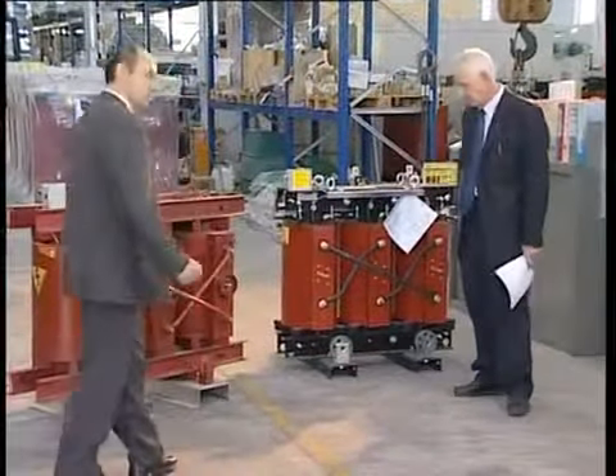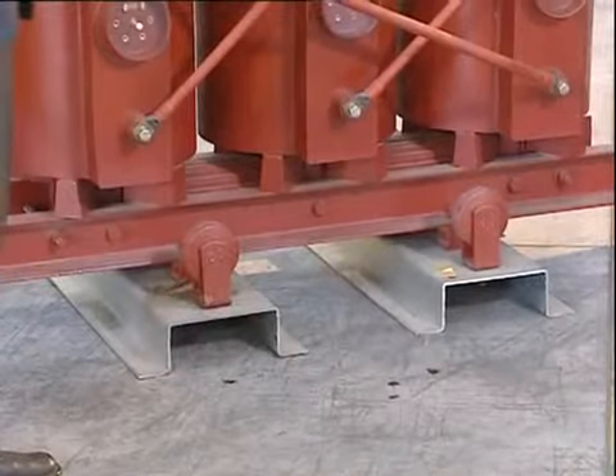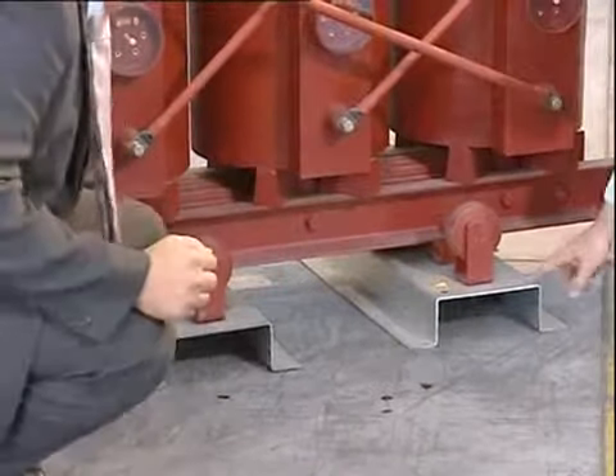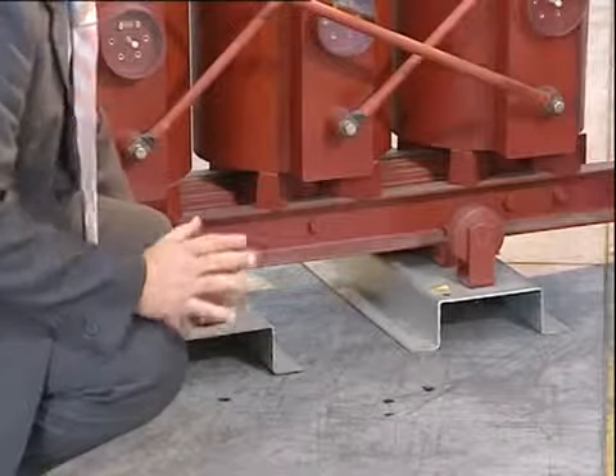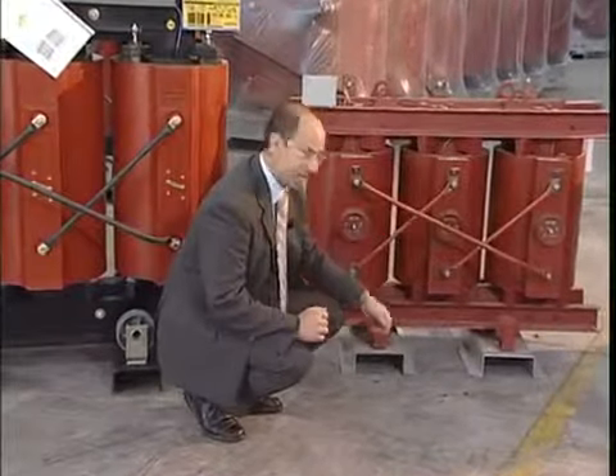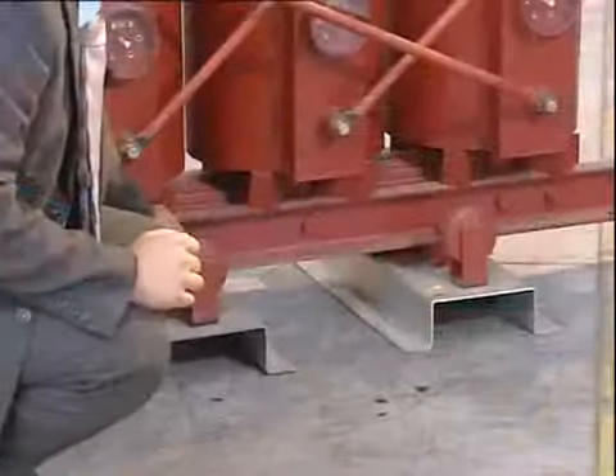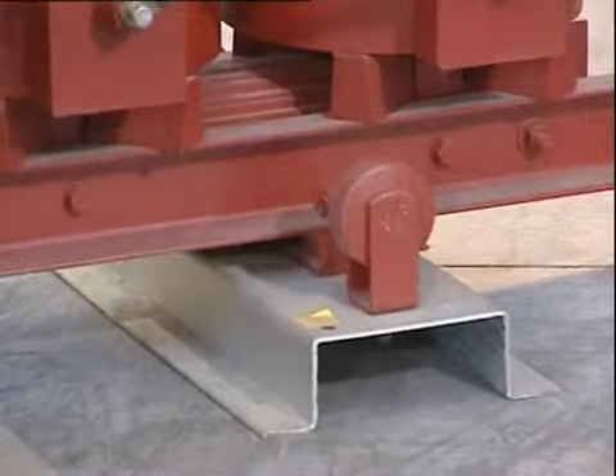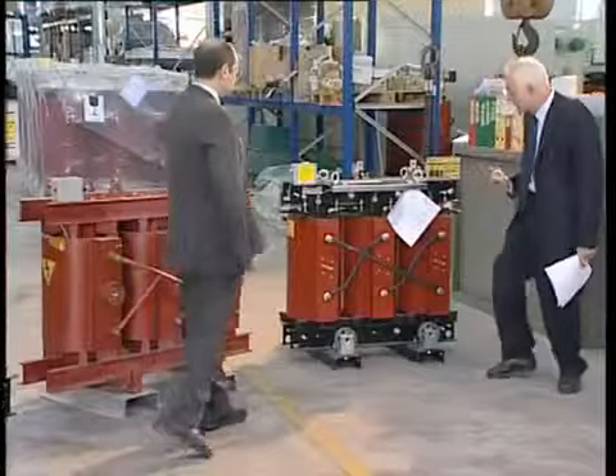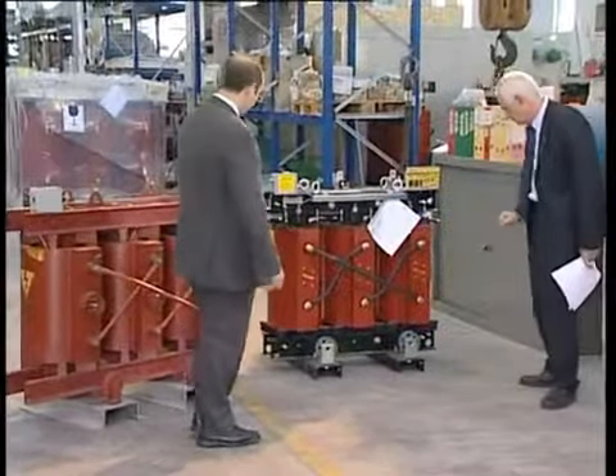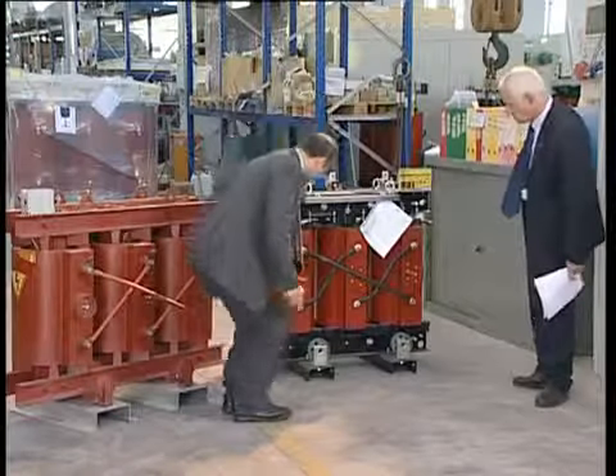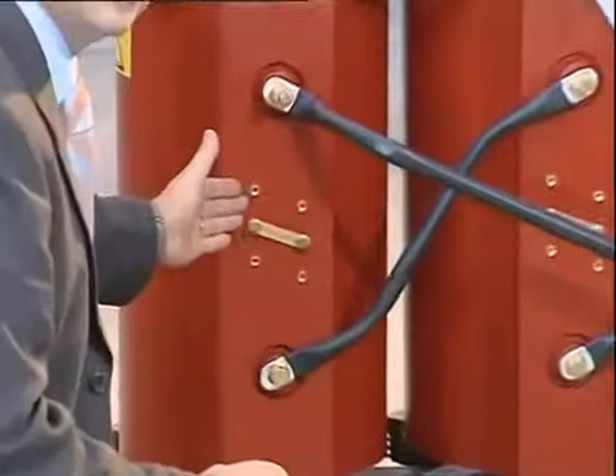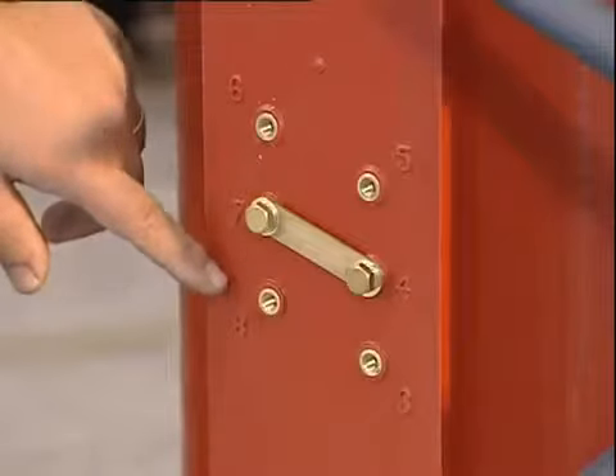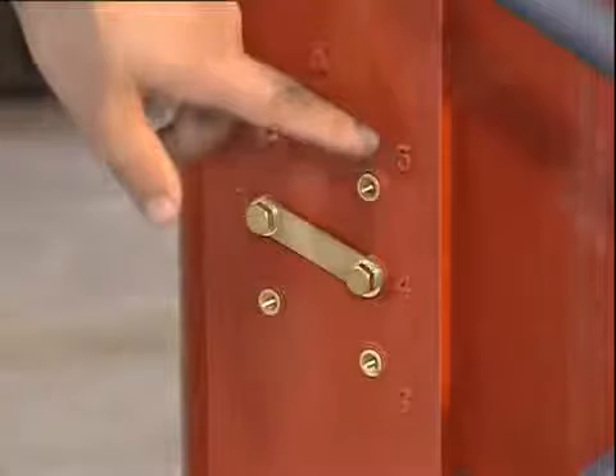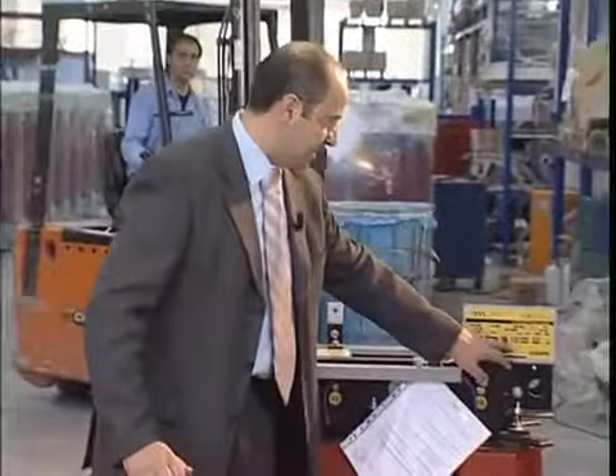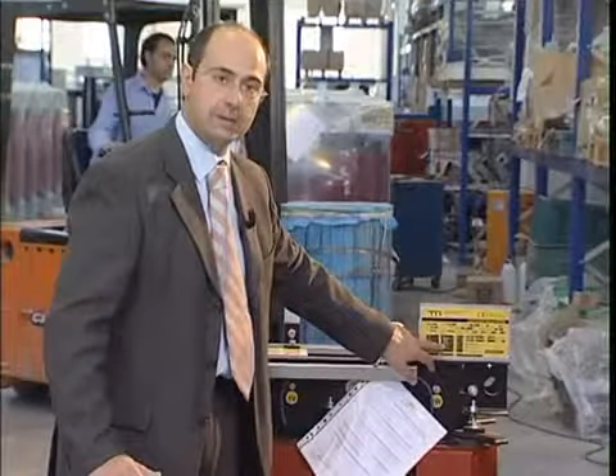Let us have a look at our competitor's transformer, which has a very strong support structure. You mean these sections? Yes, these omega-shaped bars. It is fitted with small wheels. Certainly, they are sized for the transformer's weight, which is approximately the same. But the stamped plate 100mm wheels are surely not very suitable to handle such a weight. So far from a mechanical standpoint, let us talk about the electrical features. From an electrical viewpoint, going up a little we find the voltage adjustment terminal strip, where we can notice the indelible numbers pre-stamped on the winding and specified on the rating plate. Each number combination corresponds to an input voltage of the primary winding.